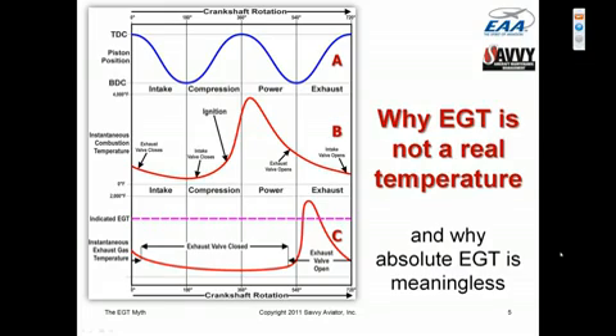To do that involves some very exotic and very expensive technology. That's not what we have. What we have is an exhaust gas temperature probe, which is a thermocouple probe mounted in the exhaust riser, typically something like 2 inches from the exhaust port. So let's go down to curve C, the bottom curve, and consider what that exhaust gas temperature probe, the thing that is providing information to our panel-mounted gauge, actually sees.